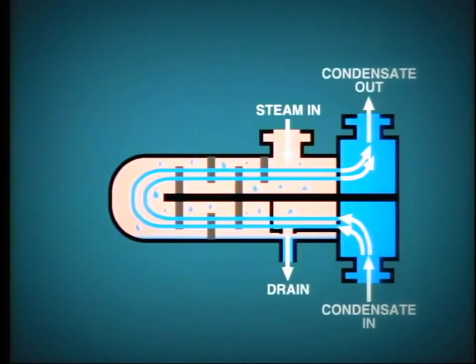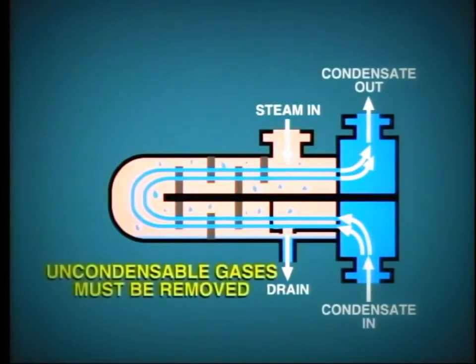As the steam condenses, it releases a small amount of dissolved gases such as oxygen and carbon dioxide. It is important that these uncondensible gases be removed, otherwise they will collect around the tubes and provide a resistance to the transfer of heat. The gases are drawn off through the vent system, which is piped back to the condenser.